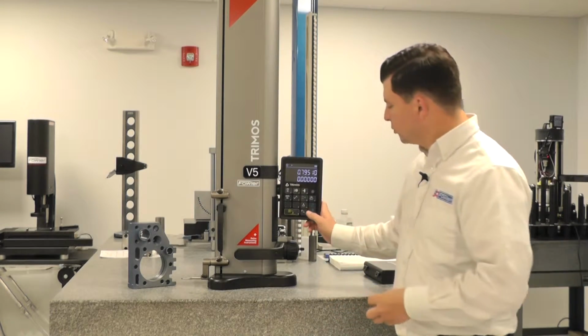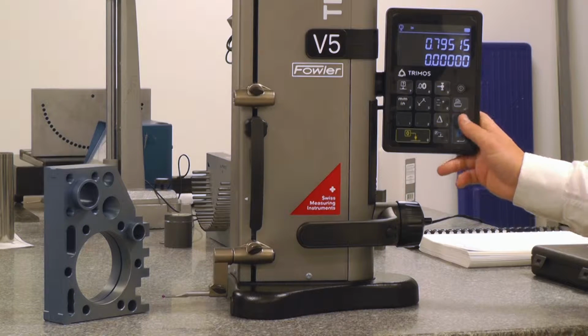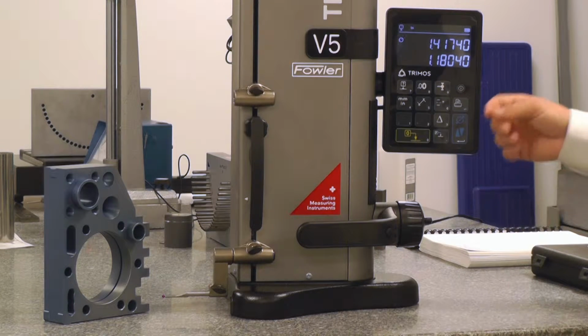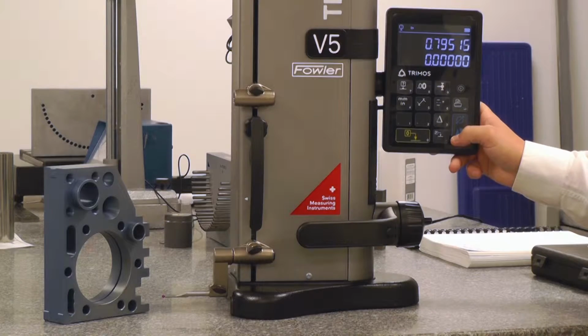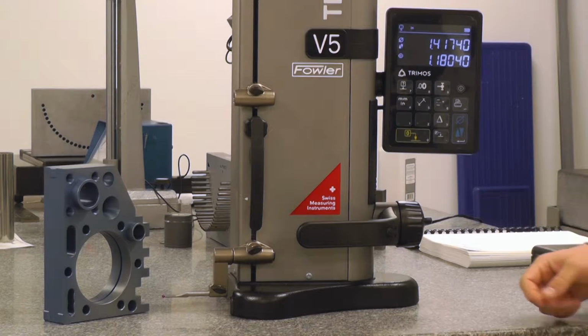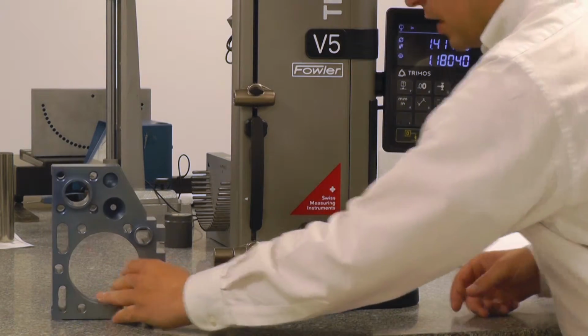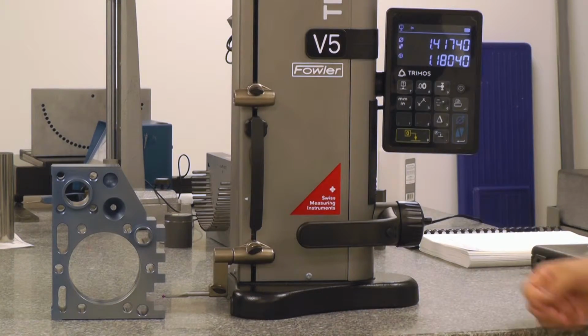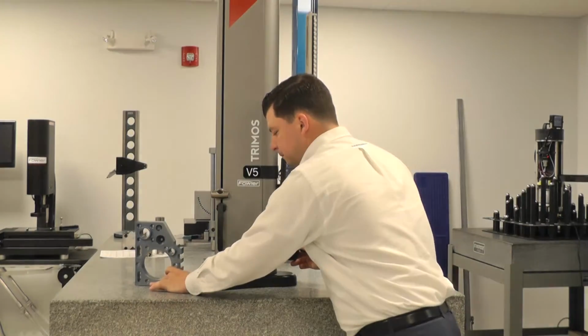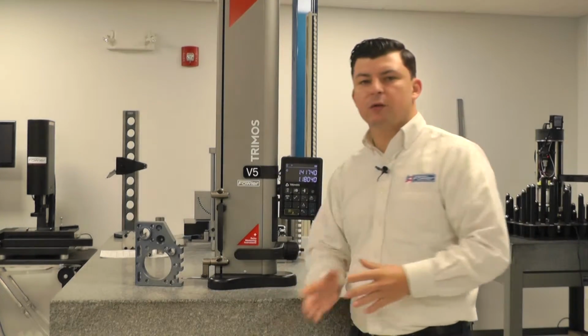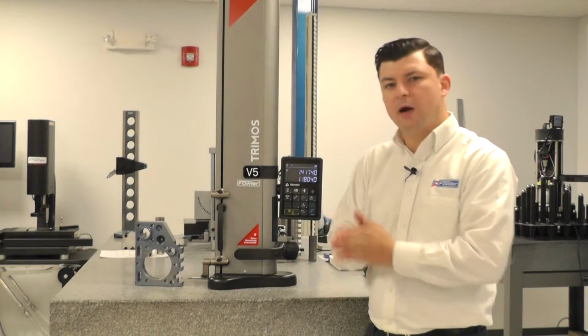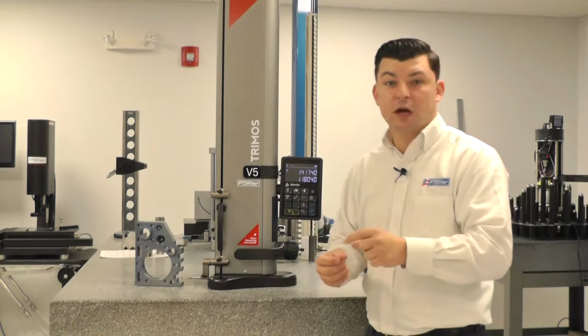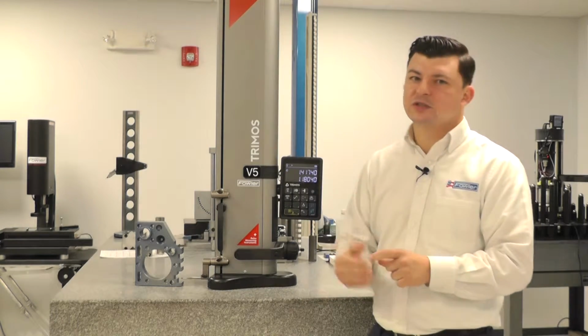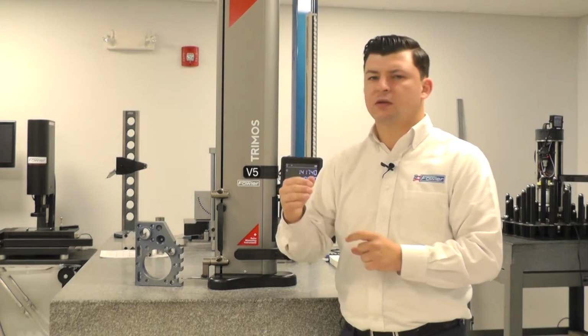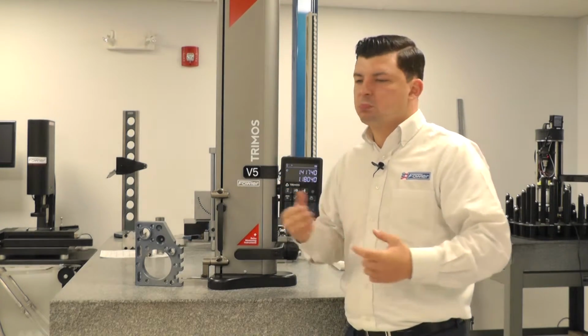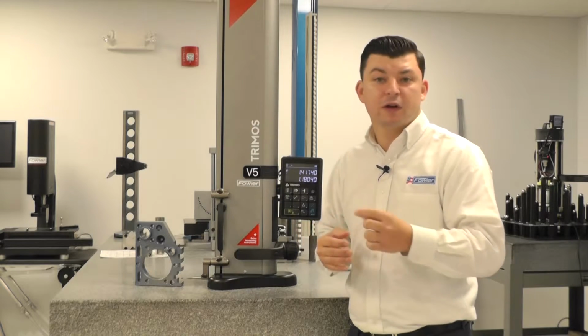If you remember, the bottom right-hand corner of the display is going to engage our diameter mode. So as we toggle that button back and forth, we go from surface height to diameter mode. Into diameter mode we'll go, and we have a series of different slots on this part here. So if I come in here, and because it's not a diameter, we don't have to worry about the sweeping process. We'll just engage our probe down and up, and we'll be able to calculate a slot width and a center line. And we can establish a zero to that center line and calculate it center to center from another slot, even center, like I said, center from the slot to a diameter if you need.